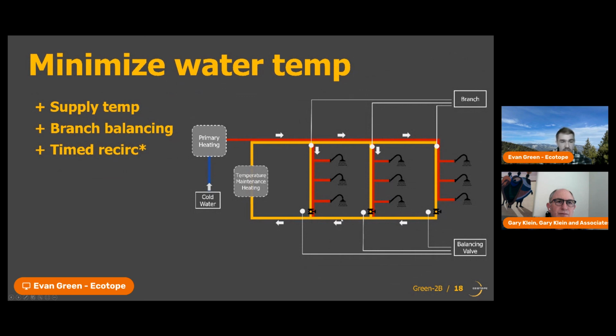And then the timed recirculation pumps are a way to create less heat loss in a system. You just need to make sure that they're applied to the proper systems for the same reasons that Christoph mentioned in his last presentation. We don't want stagnant water in these pipes. And we also want to make sure that as soon as someone turns on a tap, they're going to get instant access to this hot water. So a good application for timed recirc pumps might be an office building when we know there's not going to be occupants in that building from X time to Y time.